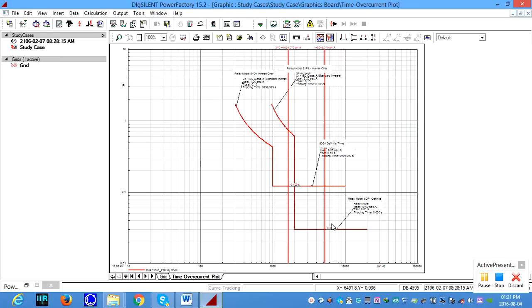At the same time, we applied a 3-phase fault, so we expect the ground element doesn't trip. So you can see the inverse ground element doesn't trip. This 999 means the relay is not tripping, and for the definite time, you can see for the ground element 999, it means the relay is not tripping. So the G stands for ground. So these two ground elements are not tripping and this one is tripping.